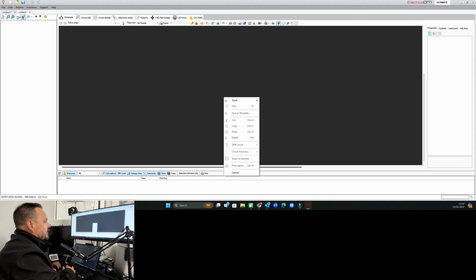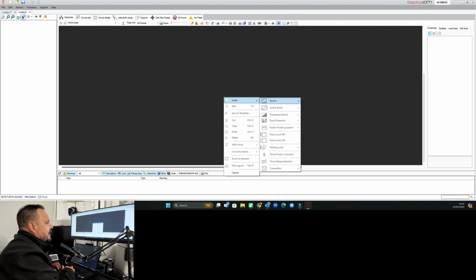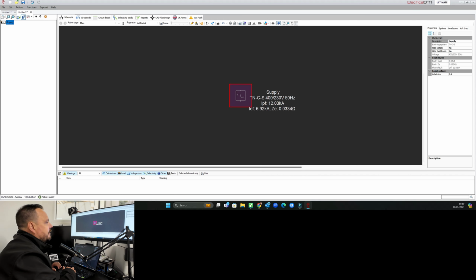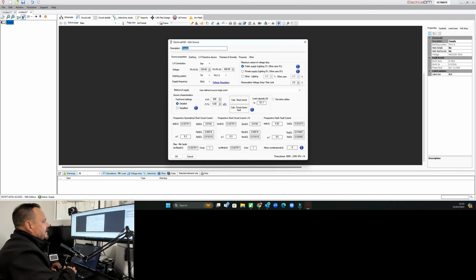So first up, we need to create our source. We do that by inserting a source, and we've got our three-phase and neutral. If we click into there, you can see it's predefined with certain values. So we can adjust our ZE. If we know what the value of ZE is on this install, we can say it's 0.14. And again, the same for our short circuit loop. If we know what that value is, you can change it. So if you know it's 6 kA, for example, pop that in there and the values shuffle about.